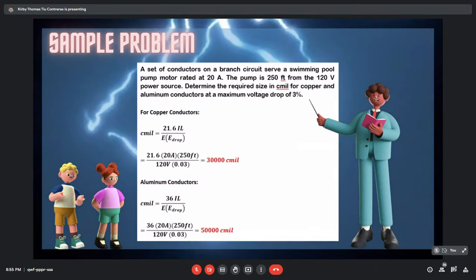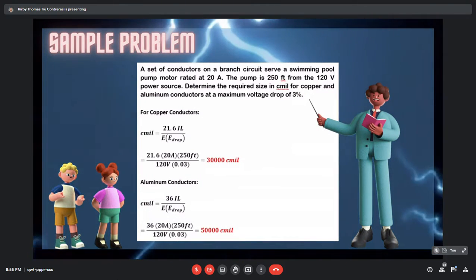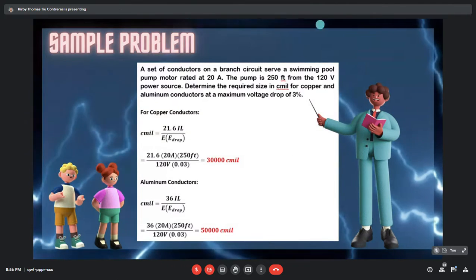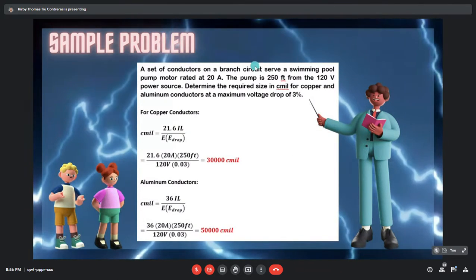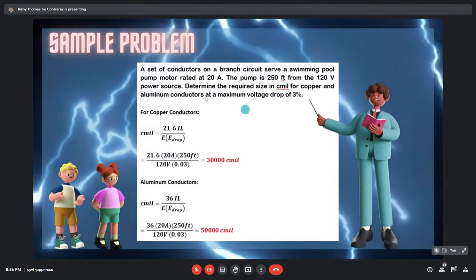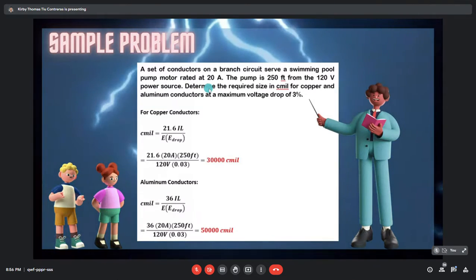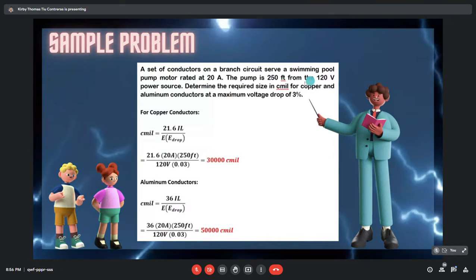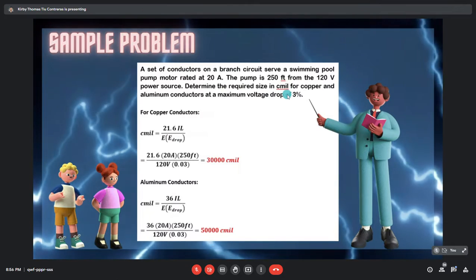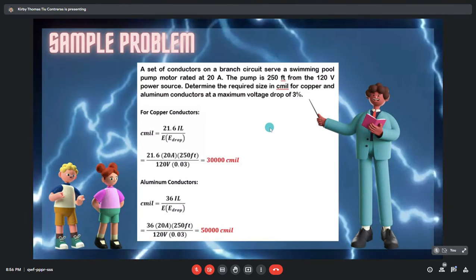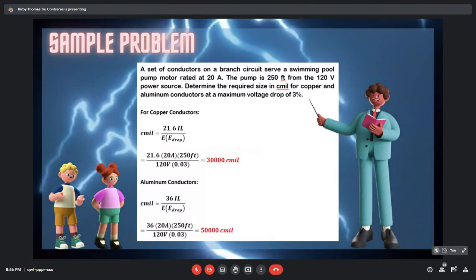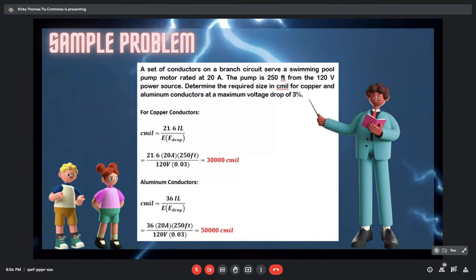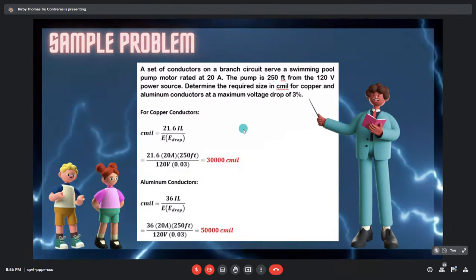So for calculating the circular mils of a conductor, or the conductor size: a set of conductors on a branch circuit serve a swimming pool pump motor rated at 20 amps. The pump is 250 feet from the 120 volts power source. Determine the required size in C-mil for copper and aluminum conductors at a maximum voltage drop of 3%.